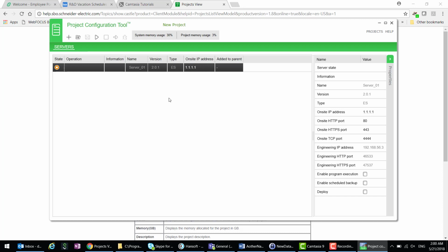The version that's in the live AS is obviously determined entirely by the version that was installed into that automation server by the device administrator. When you do a backup of that automation server and then use that to restore into the PCT, the version that actually shows up in the PCT is whatever version it was that was available for that major version when you installed the project configuration tool.